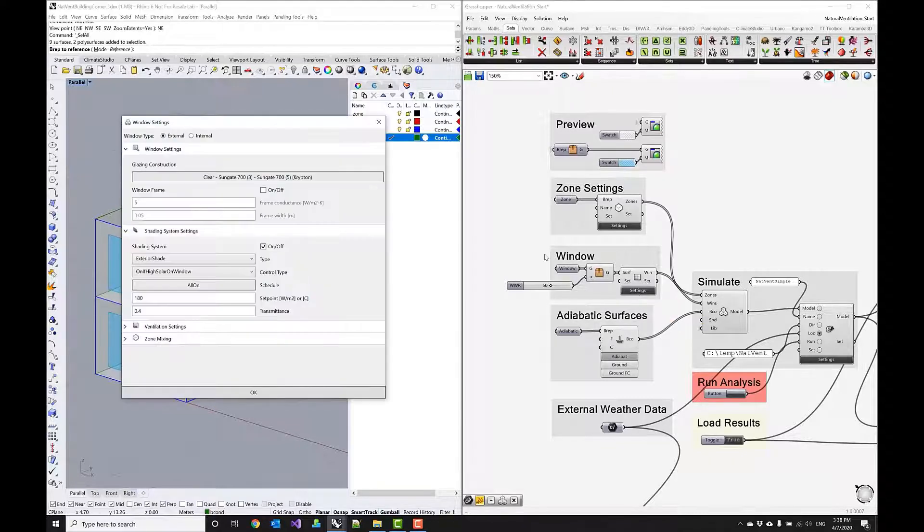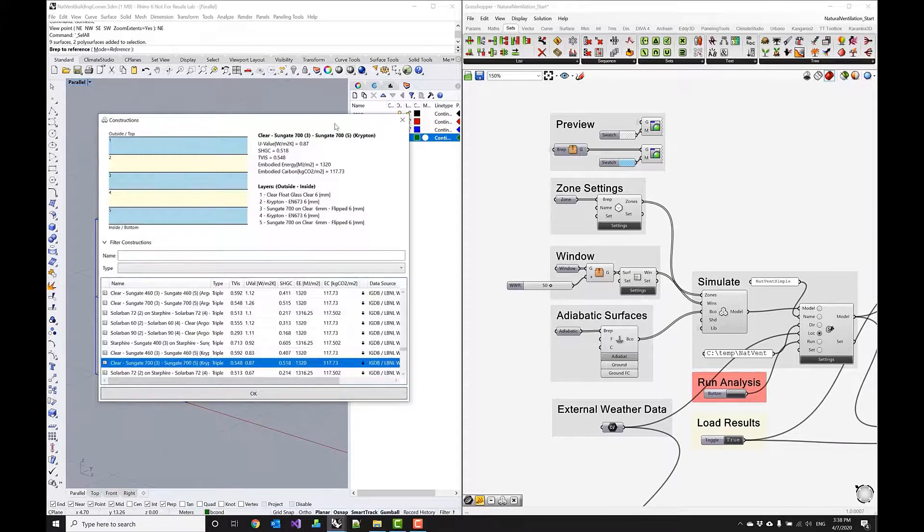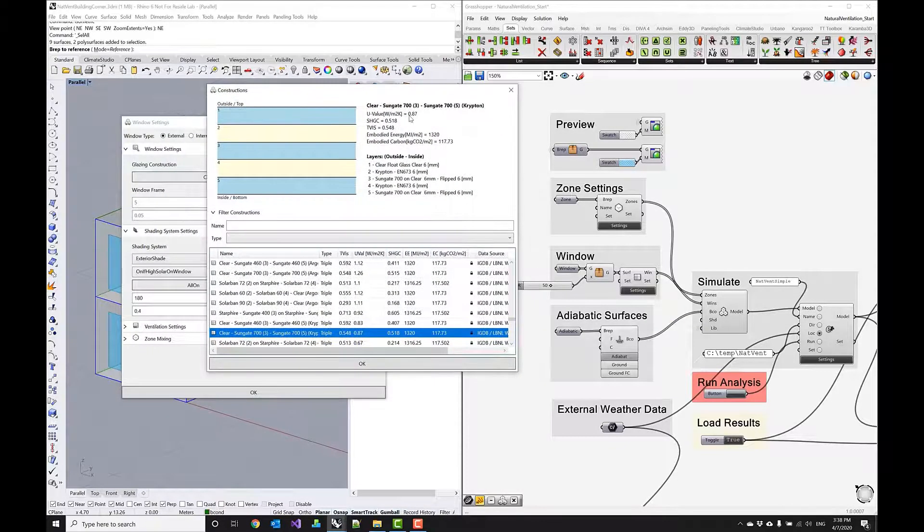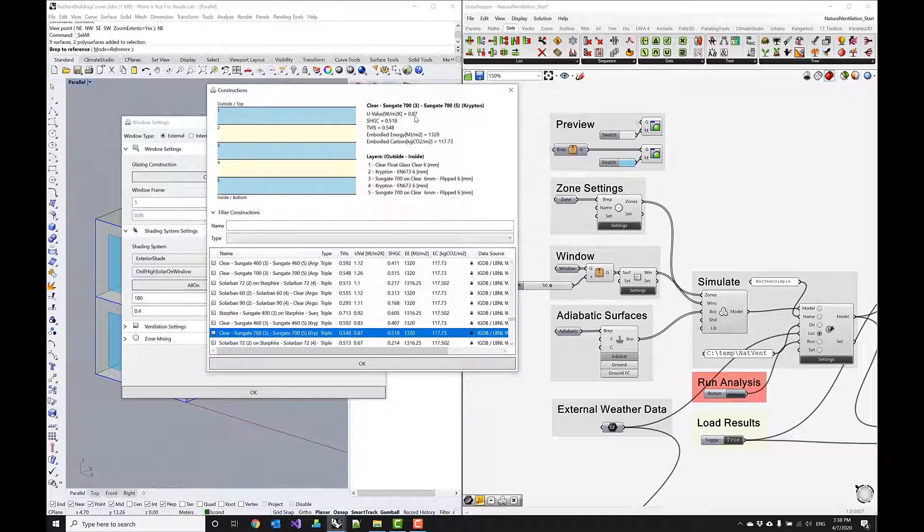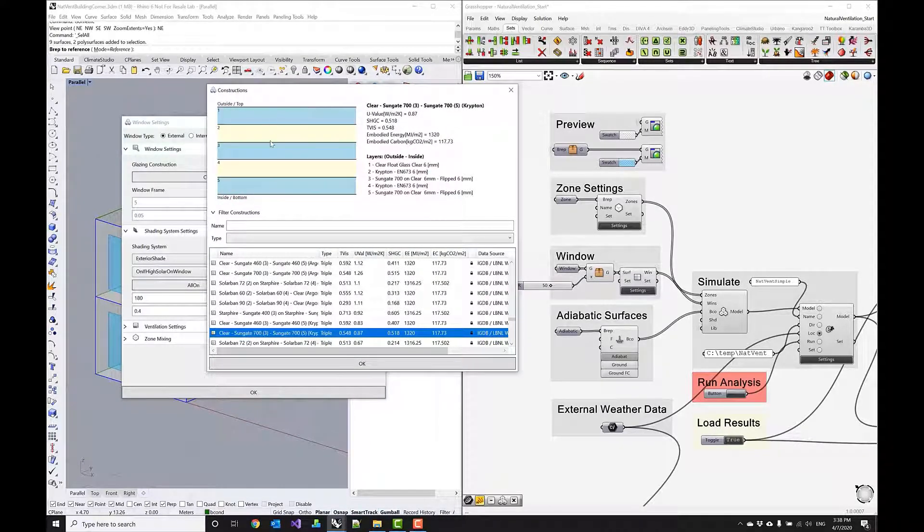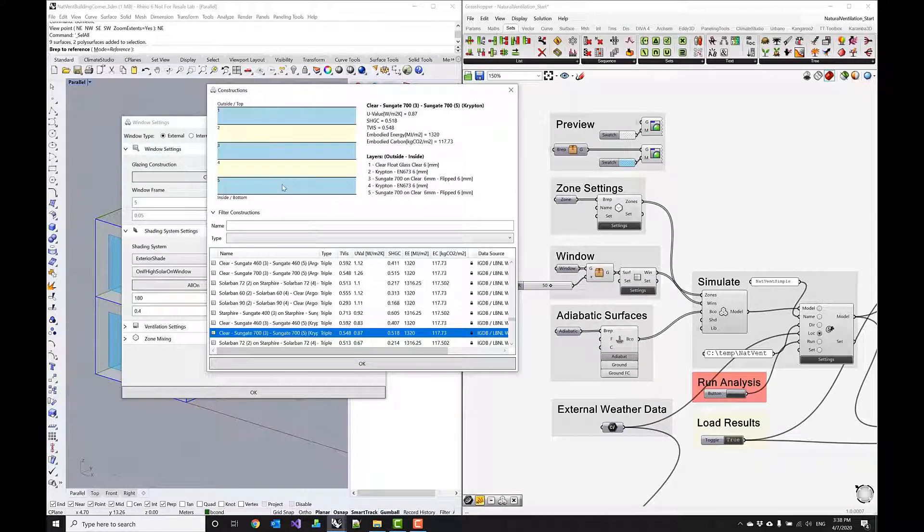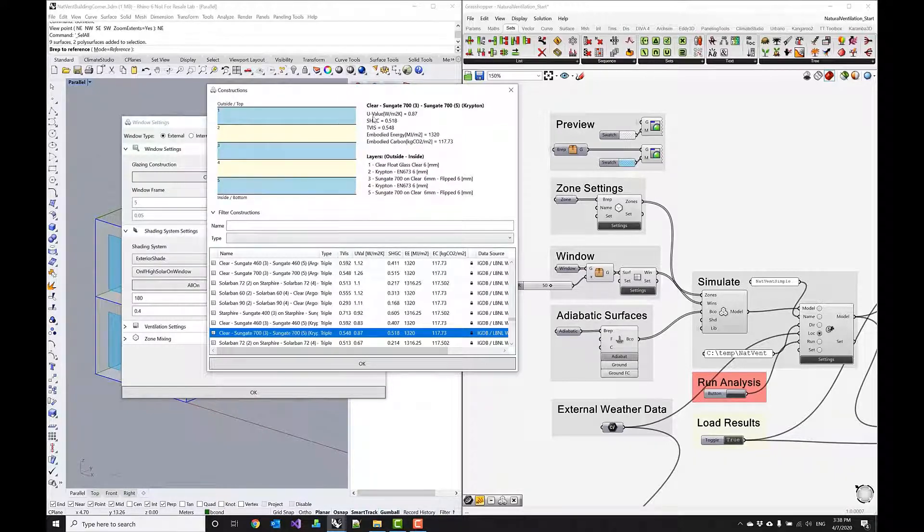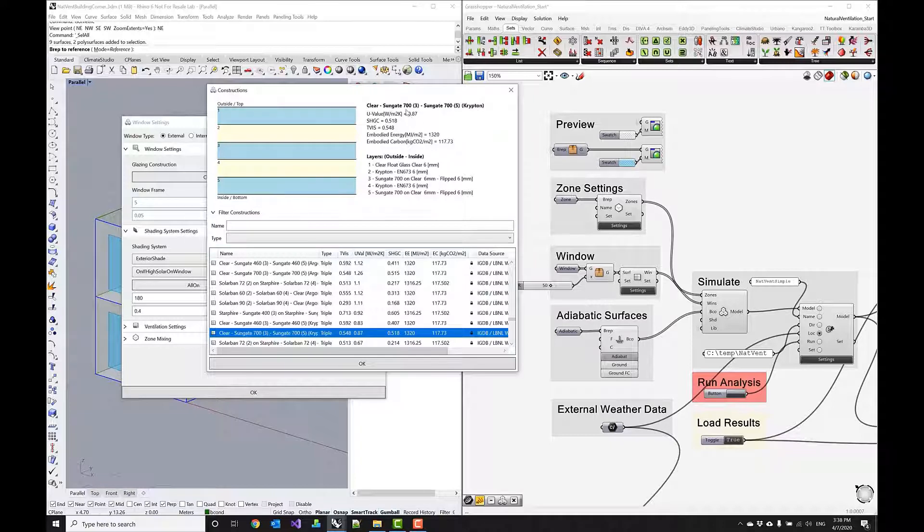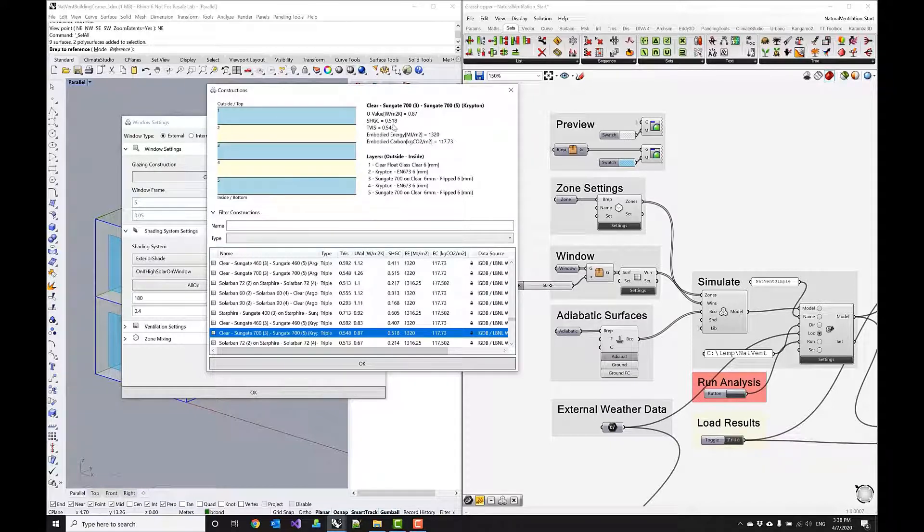triple pane glass with the u-value of 0.8 and a solar heat gain coefficient of 0.5 so it's a fairly good setup for the envelope. The assumption here is that Frankfurt is a heating dominated climate and therefore I want to pick a fairly low u-value and a higher solar heat gain coefficient so I can make use of passive solar gains.